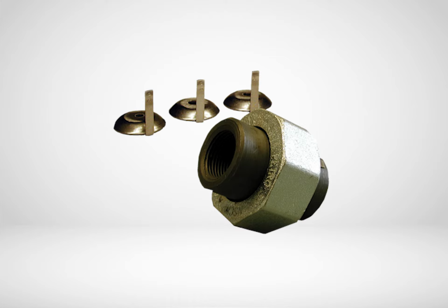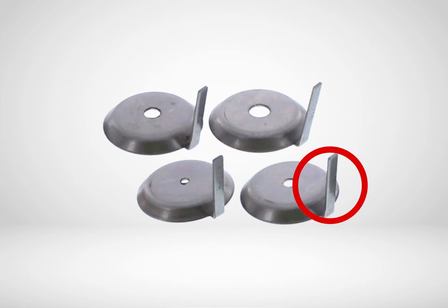Orifice unions are shipped with various size openings which can be identified on the tab. If flashing continues to be an issue, consider switching out the orifice plate with one with a smaller diameter opening.